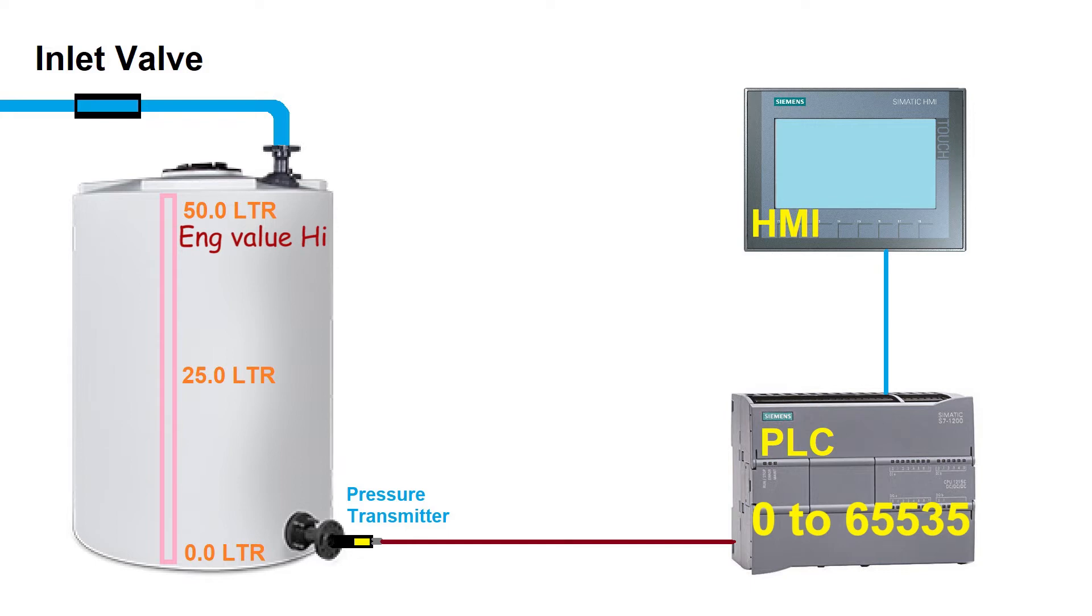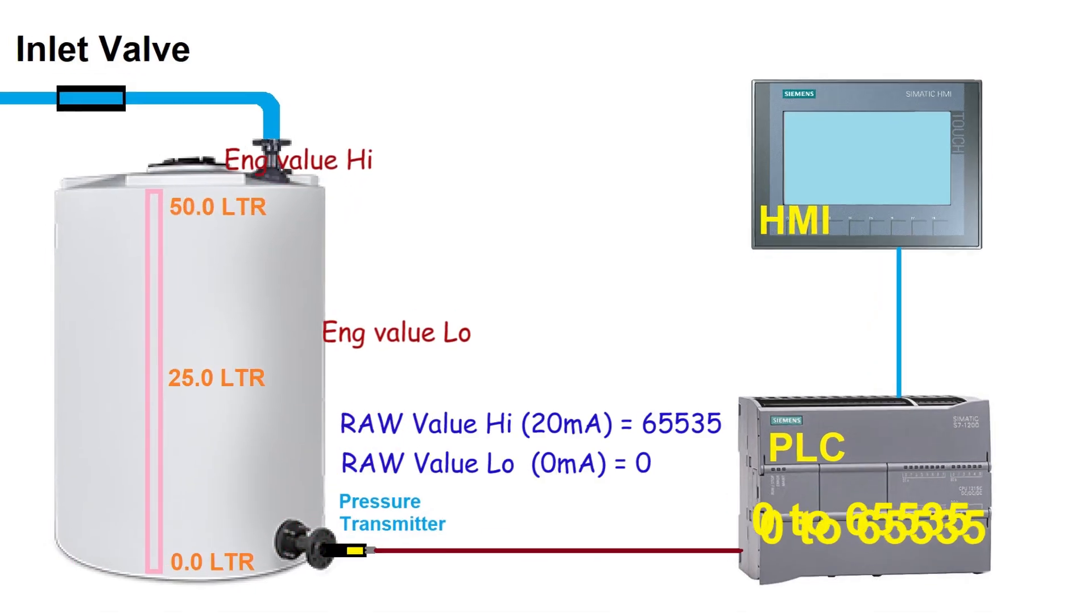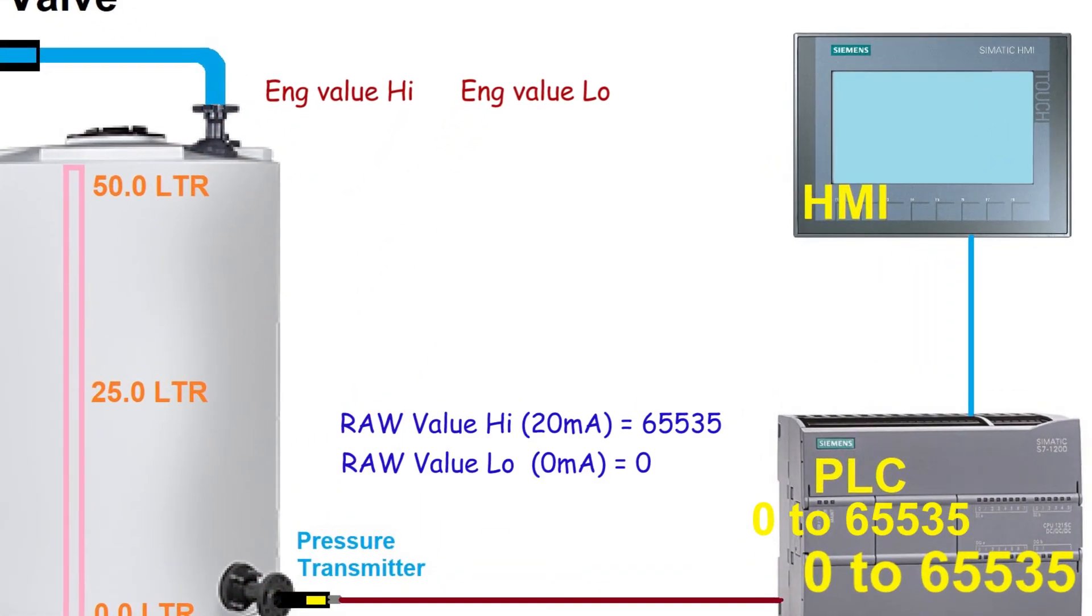So we have here engineering high value which is 50 liters and low value is 0 liters. It is the minimum and the maximum values for the tank level. First we will take engineering high value and then minus engineering low value which is 50 minus 0 equals 50 liters.